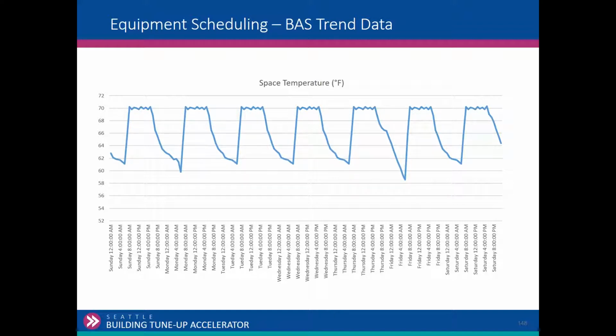So here's a trend of space temperature versus time. So, okay, we can see what that schedule is. So that's another way of verifying that. We could also use a data logger to trend the schedule. These are pretty accurate. They'll tell you what time the system's coming on, what times it's going off. Weekends, this basically will tell us approximate set points. It shows us kind of what our low limits are. So we can verify scheduling through trending. We can verify scheduling through data logging.